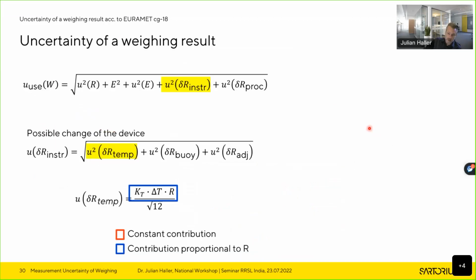Next one, as mentioned, is a possible change of the device, and this is mainly due to possible temperature changes. As a calibration lab, we do not know if the temperature might change in the future at the site of installation. So we have to make an assumption of how much the temperature might change at this installation site, and then use this estimation together with a sensitivity coefficient for temperature of a weighing instrument that is usually given in the data sheet of a weighing instrument.